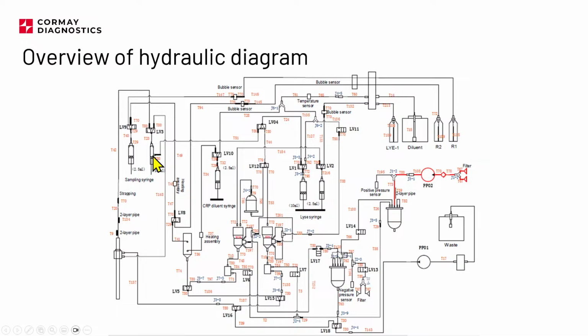The sampling syringe has a bottom port and a top port. The reason for that is that this whole volume should be completely filled with diluent, and only a small metallic piston will change the internal volume. This also allows us to aspirate those 20 microliters of blood from the sample, and later aspirate a little bit more from the WBC chamber and transfer it to the RBC chamber. Right? So this complete line should be filled completely with diluent. We don't want any air bubbles, any air pockets here. This is the reason why this thing is made in such a way.